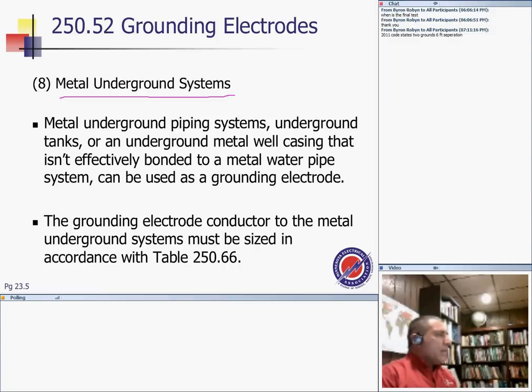Underground systems, any metal underground system, guys. Underground tanks, for example, an underground metal well casing that's not bonded to the metal water pipe, because if it's bonded, then it's part of the equivalent of a conductor and can be used as a grounding electrode. A metal casing of a well that is in direct contact with Mother Earth could act as one. If you were to guess, Jacob, my friend, what is the grounding electrode system? It is a metallic object in direct contact with Earth, basically.